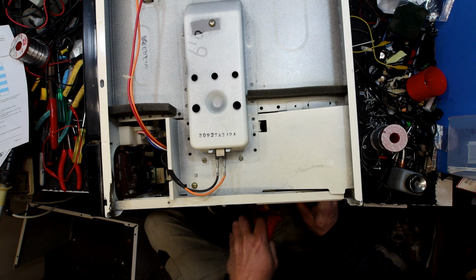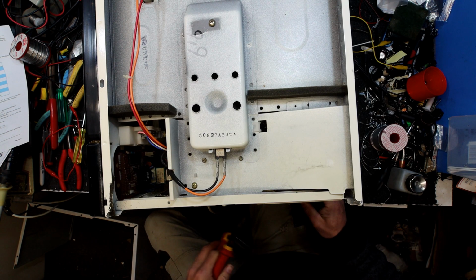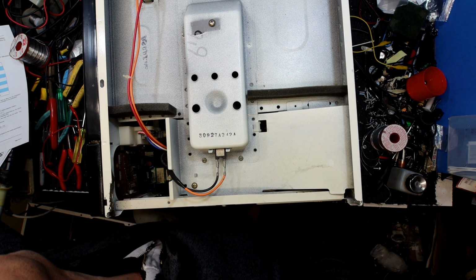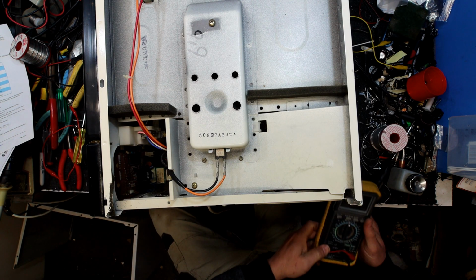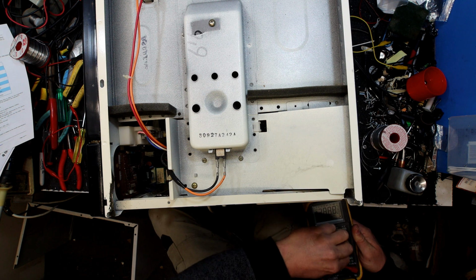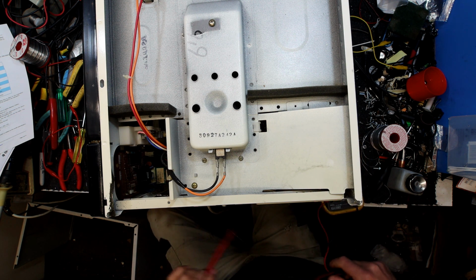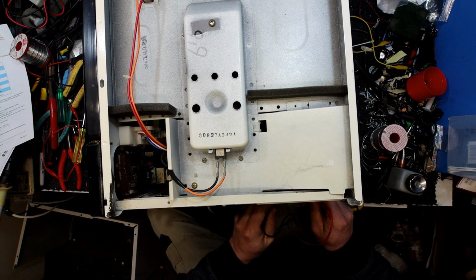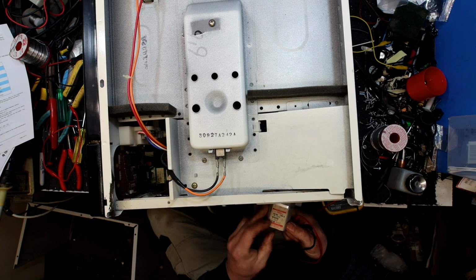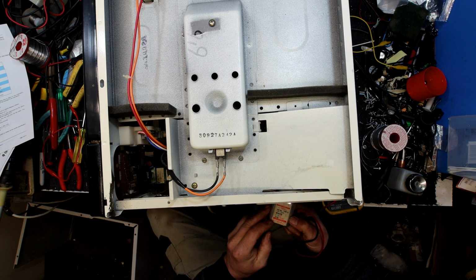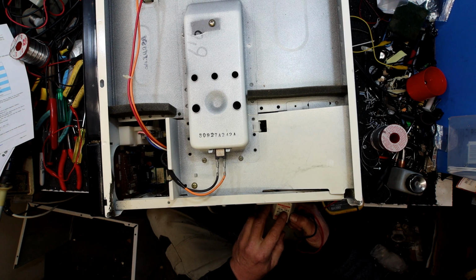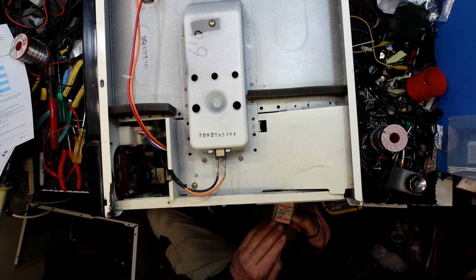We disconnect one side of this - the short protector could probably stay in the circuit. But let's do a capacitor test. It'll no doubt be good - 1.17, and it's rated 1.13, so if anything it's better than rated. It's a Nichicon, no PCBs. It should have a 10 mega ohm discharge resistor, but like I say, never trust the discharge resistor to work.